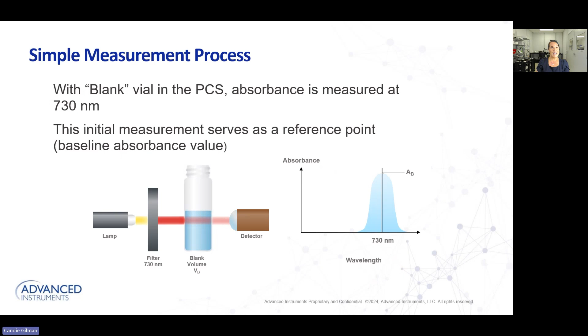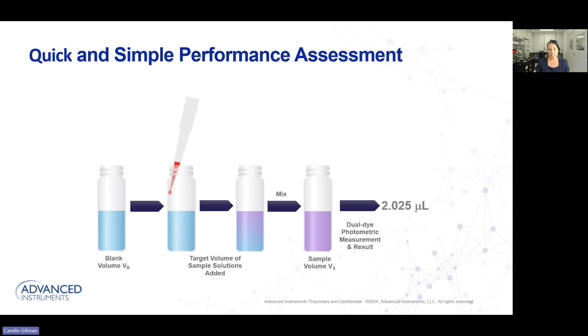I aspirate some red dye. Again, the red dye is the measurement step, if you will. There's a vortex mixer that mixes the dyes together inside the instrument, and my volume quickly appears. So what's happening when I add that red dye? After I've added the red dye, there's a second filter that reads at 520 nanometers, and that will read the absorbance of the red dye. And together, the absorbance of the red dye and the blue dye, we will calculate your sample volume using Beer-Lambert law and using that ratiometric measurement and calculation for you.